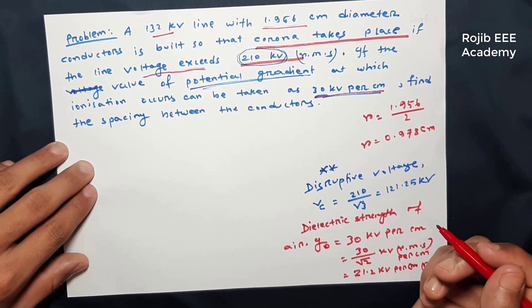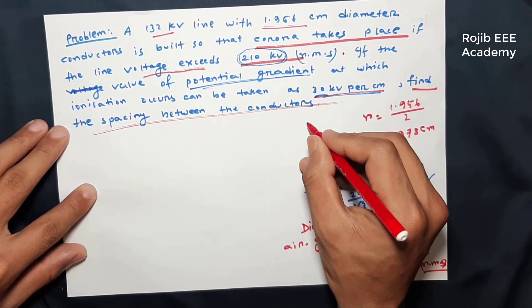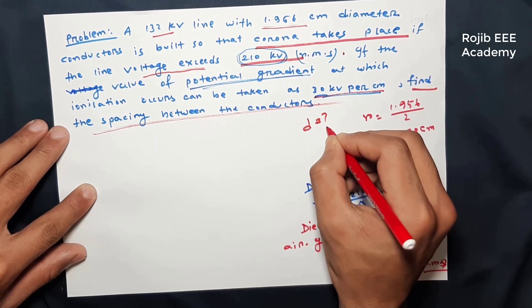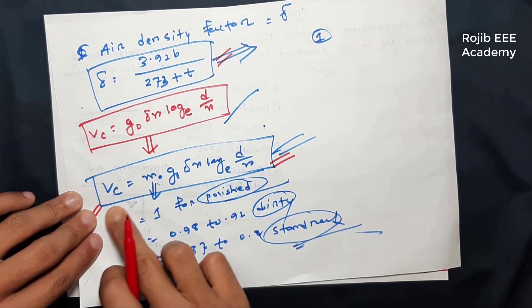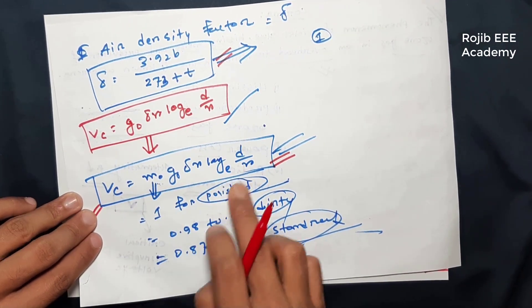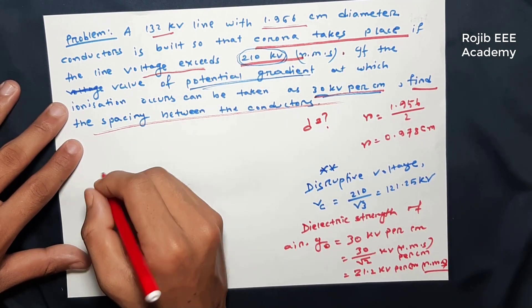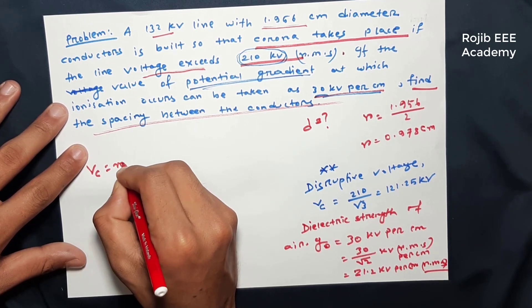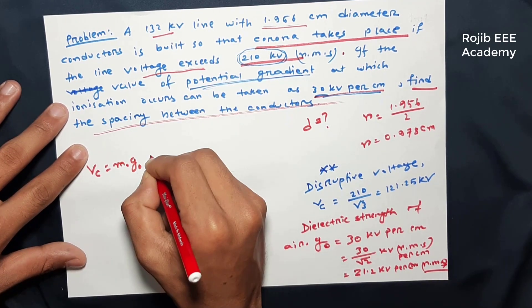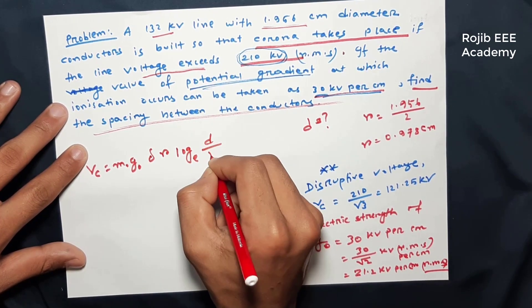Now we need to calculate the spacing between the conductors — that means d is equal to what? We have the disruptive voltage here. Vc is equal to m0 · g0 · δ · r · log_e(d/r). We have seen this formula and will now apply it.